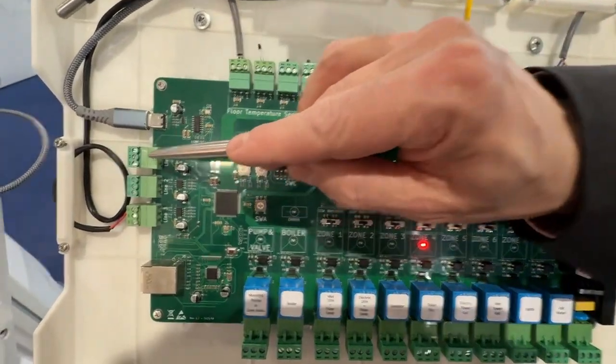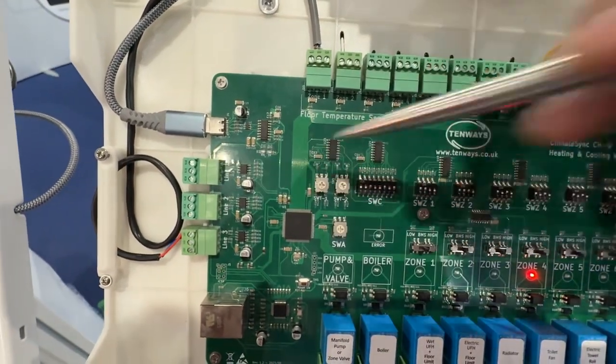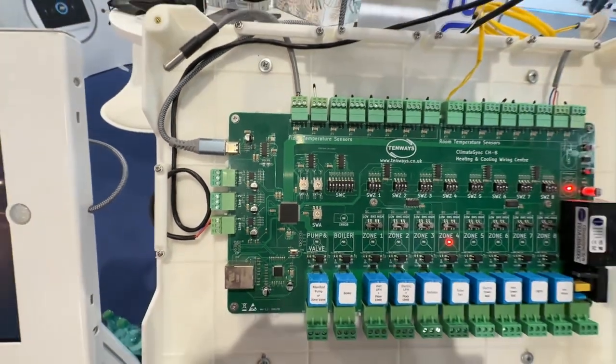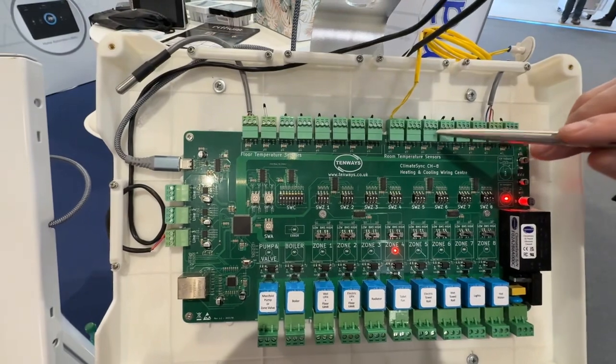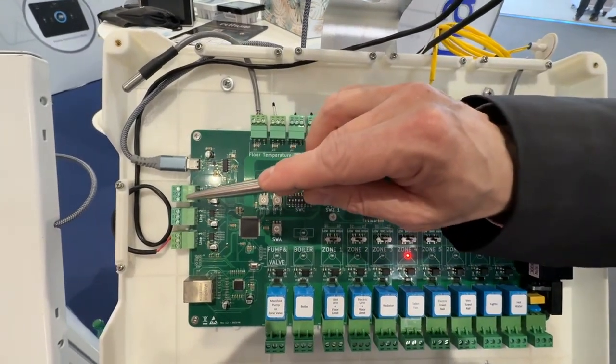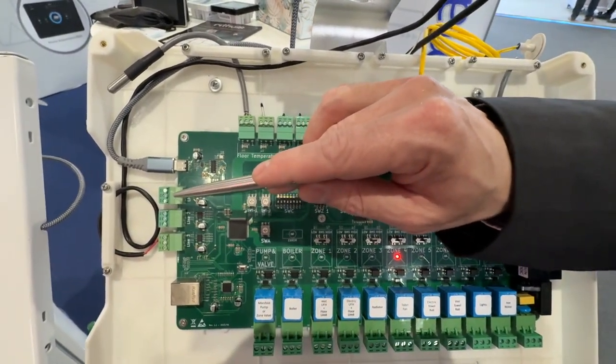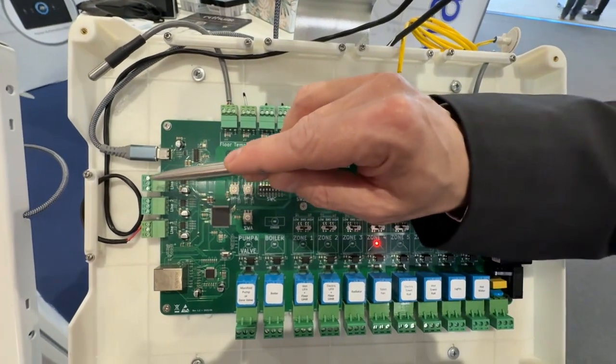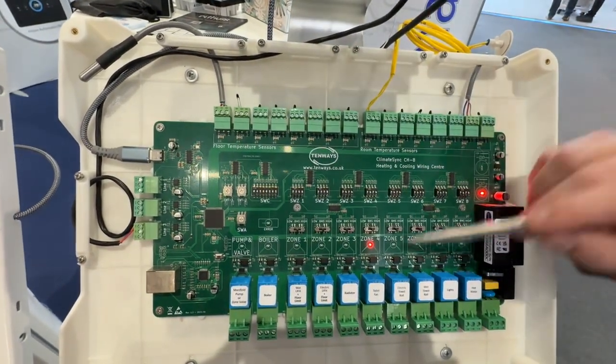The 3 Modbus connections: line 1 will communicate with the air conditioning to interlock the air conditioning and to feed the room temperature read by the ClimateSync into the air conditioning, so the air conditioning continues following its own logic by operating together with the ClimateSync and interlocking with the heating.